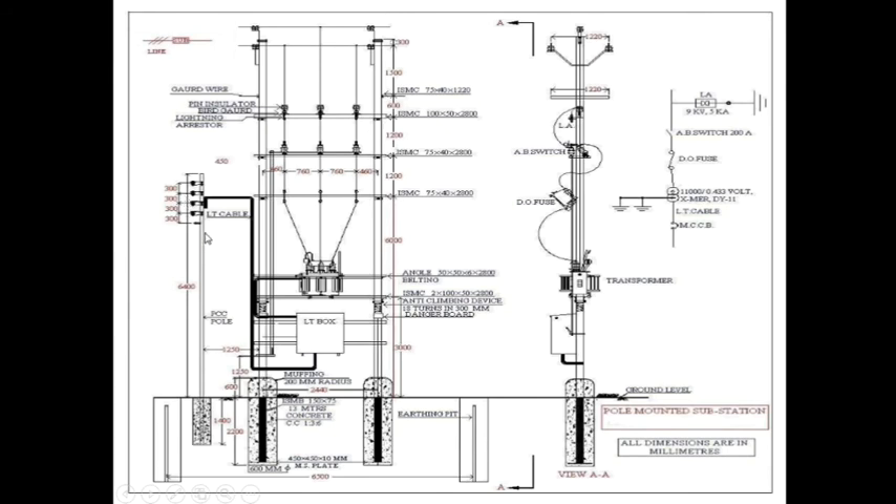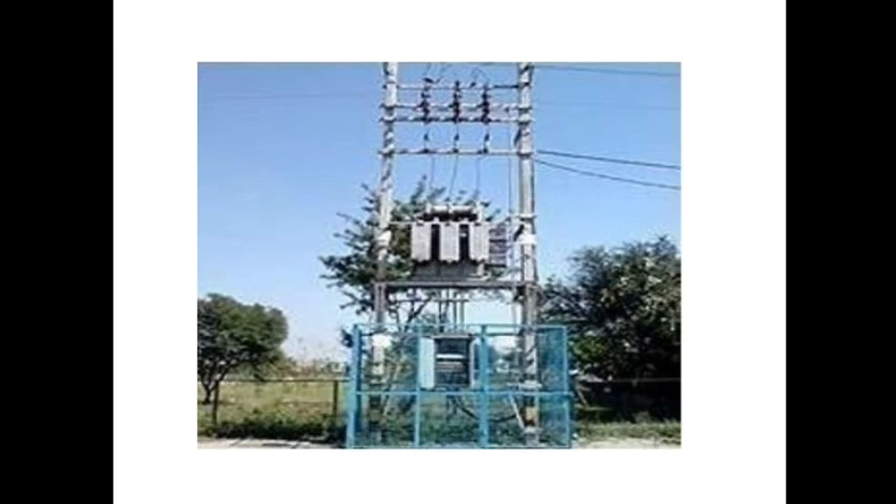This is a PC's pole mounted substation. This is the transformer. There are three earthings. One is for the neutral of the transformer. Another one is earthing for the lightning arrestor. Another one is earthing for all the metallic parts of the substation — transformer body, channel, all metallic parts should be earthed.